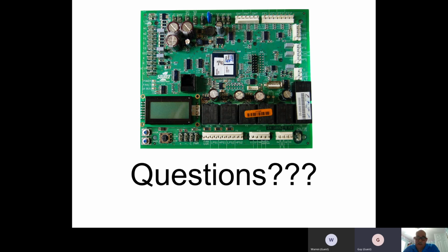I believe they do have a mixed air sensor, and what that sensor is doing is actually looking at the air it's bringing in from outside, mixing with the return air, and it's one of the things that allows the unit to calculate heat content of the air. And so there's three basic controls or three different options you can have on an economizer. One is a dry bulb changeover. In other words, it just looks at the air temperature outside and the air temperature inside and says it's okay to economize or open the economizer.